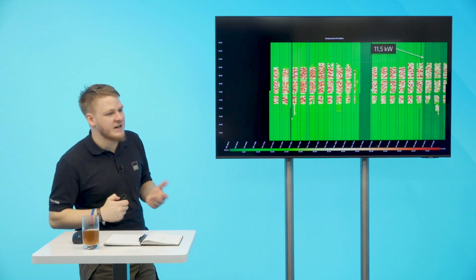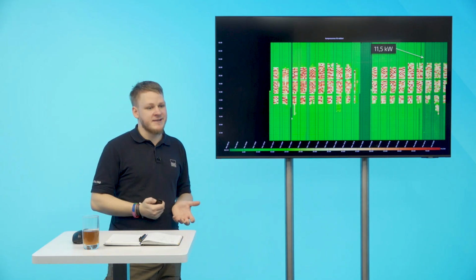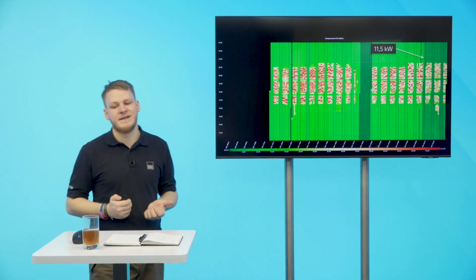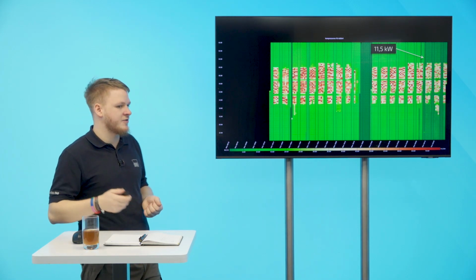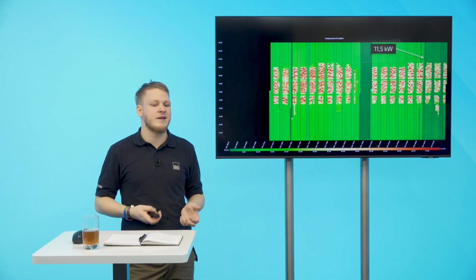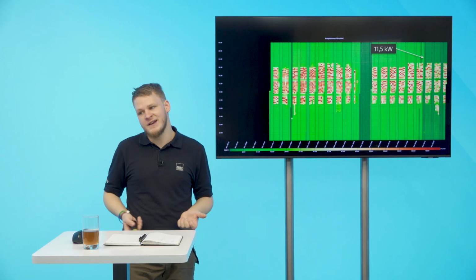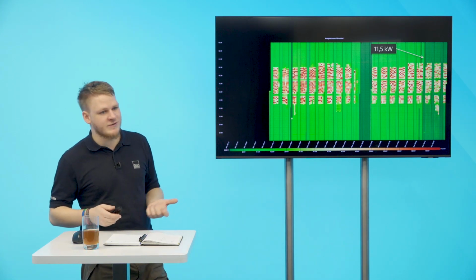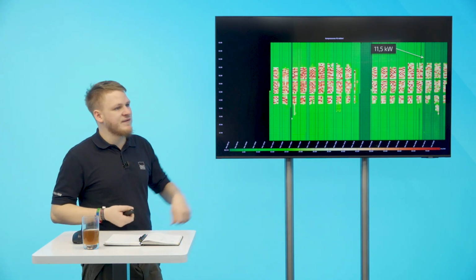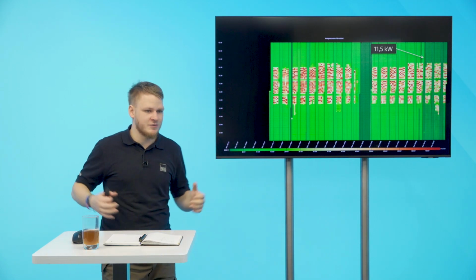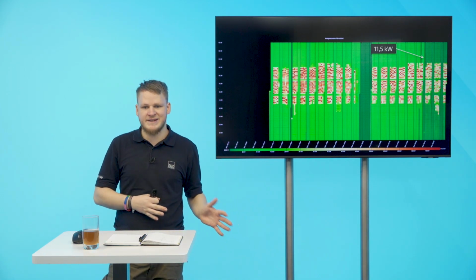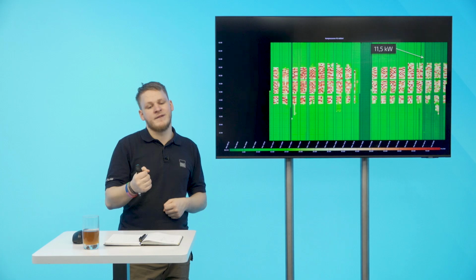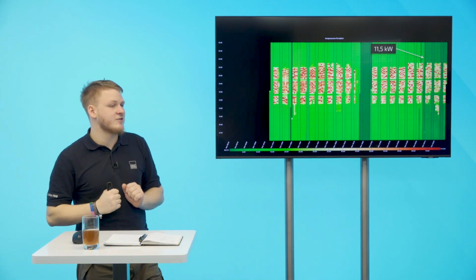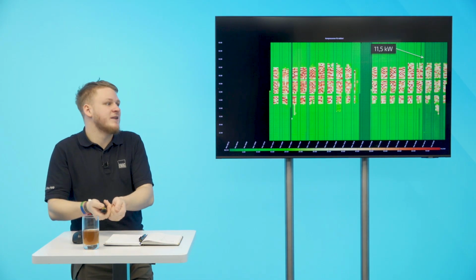So we walked around looking for the leak. Usually, monthly, we walk around with a sensor device to check all the airlines for leaks, but we didn't find anything. So the next step was walking around production at the end of shift and closing off valves to isolate different parts of the factory, to see if closing off a circuit made the energy usage drop, since you can't simply look into the line.